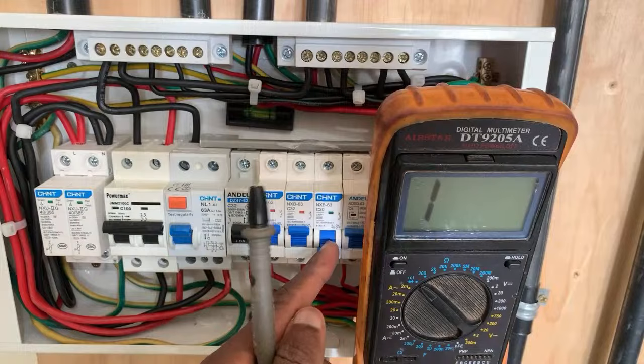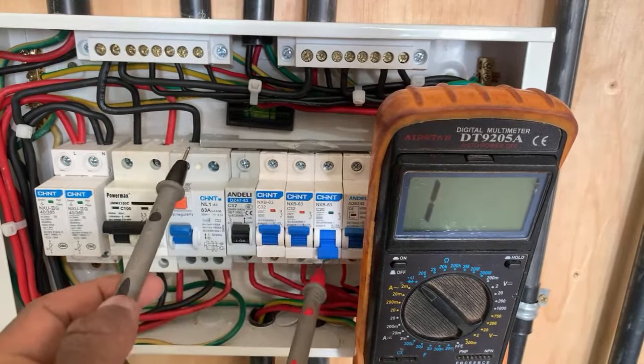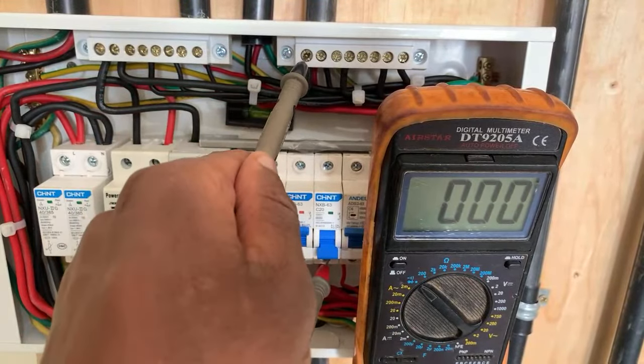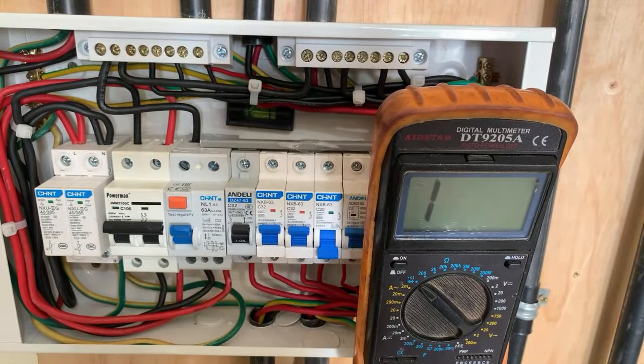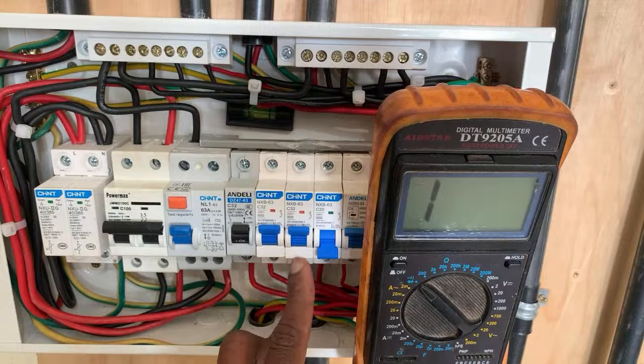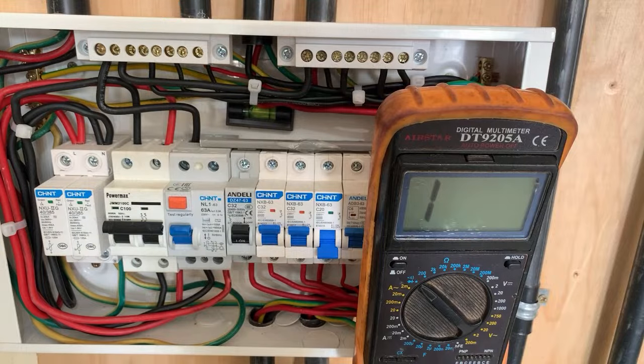But before you raise this MCB or turn it on, you must again come back and do that troubleshooting. If there's that beep, you need to check the entire wiring, especially at the socket. If there is a problem, you solve it at the socket level, and you ensure that it is very much resolved before you raise your circuit breaker. It's not just a matter of turning it on simply because it is supposed to be on. Like I've said, if you do that, there is a likelihood of some fire or some heavy sparking. So you need to take care of that.